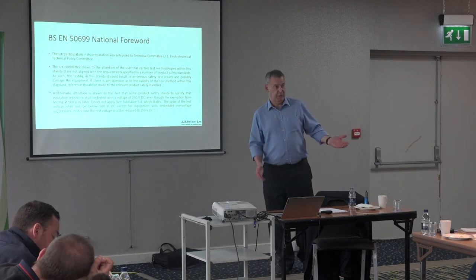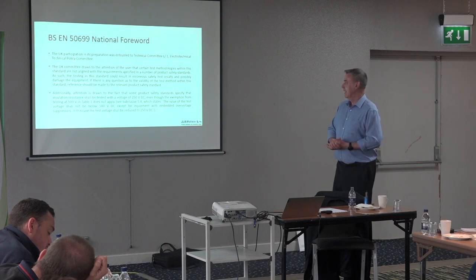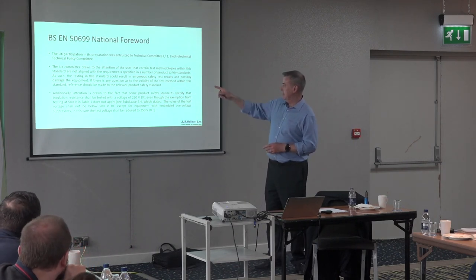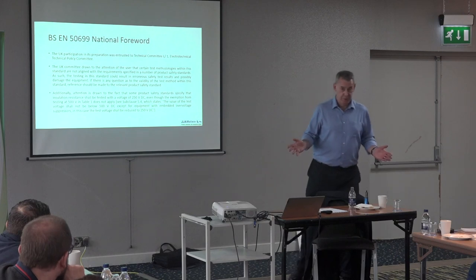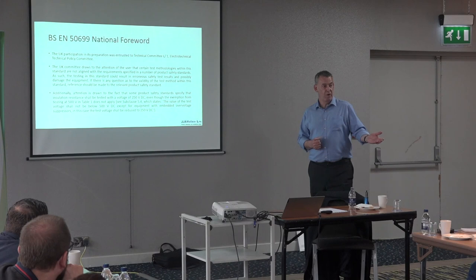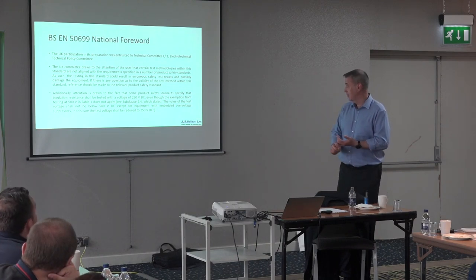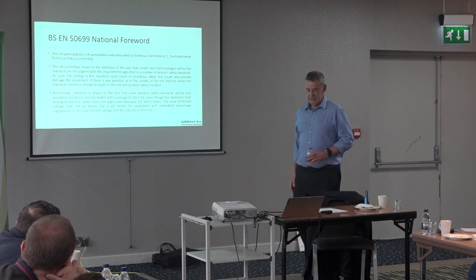BSI's original proposed national foreword was basically saying the Code of Practice is right and this standard is going to damage everything. It was toned down, but they put in a warning saying testing in this standard could result in erroneous safety results and possibly damage equipment — which in my personal opinion is absolute garbage. These are tests we've been doing for 30-plus years: earth at 200 milliamps, insulation testing at 500 volts. It isn't going to damage anything.